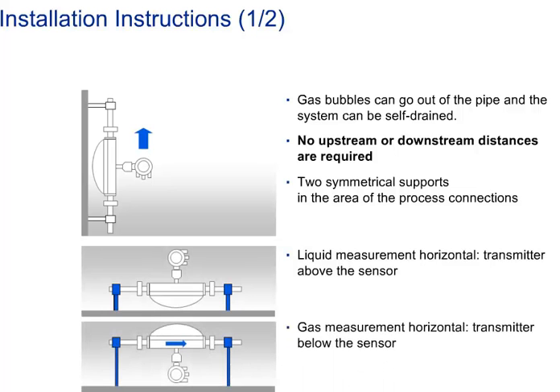For gas measurements in horizontal orientation, the transmitter should be below the sensor to avoid any condensates remaining in the sensor.